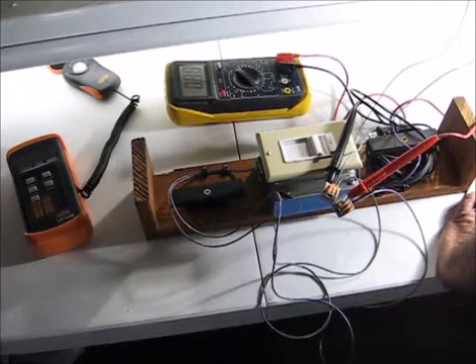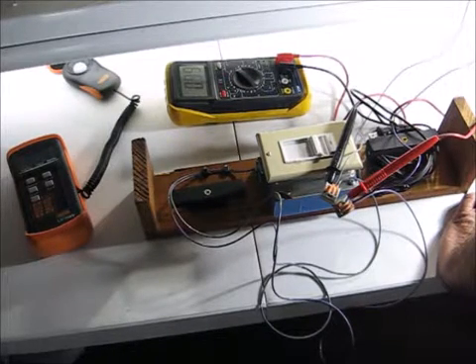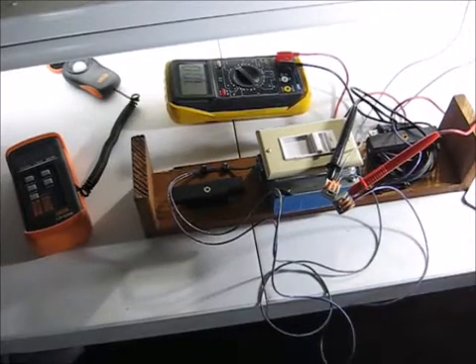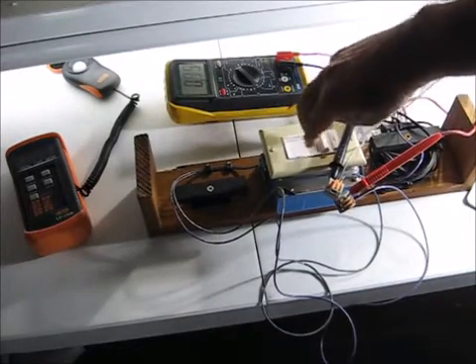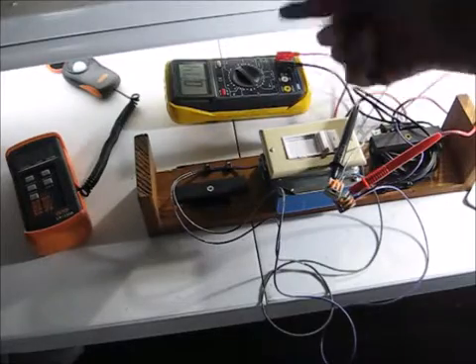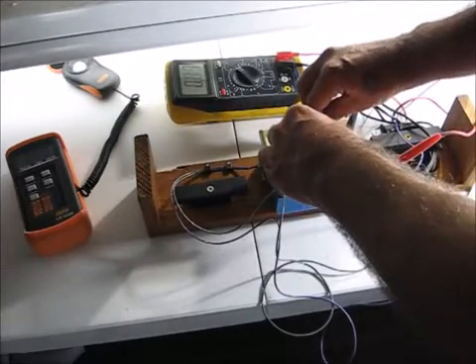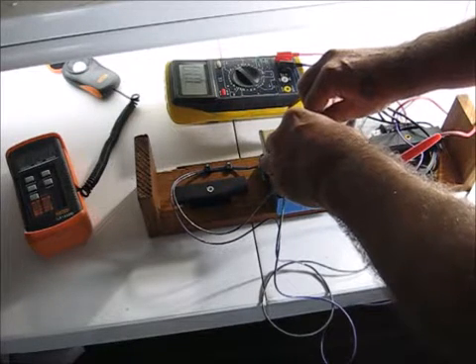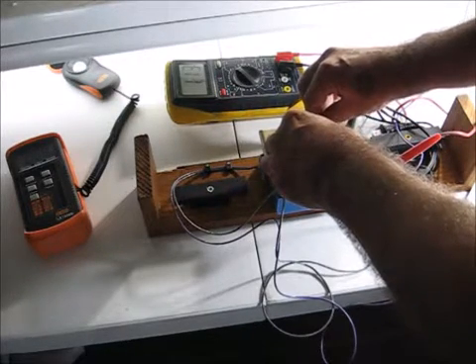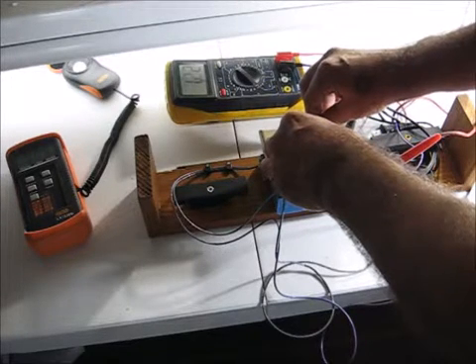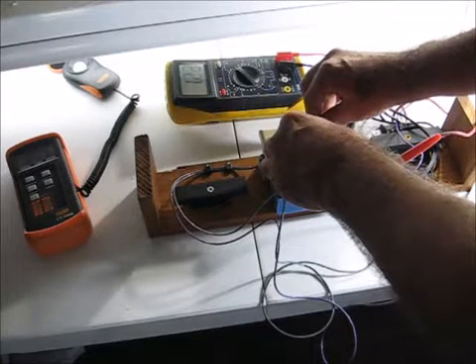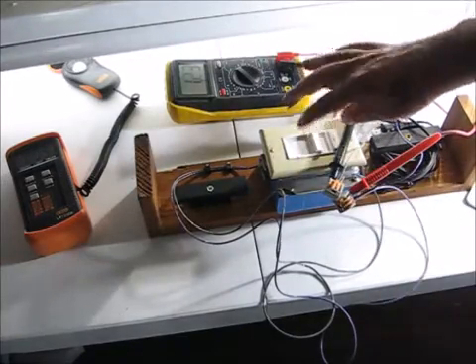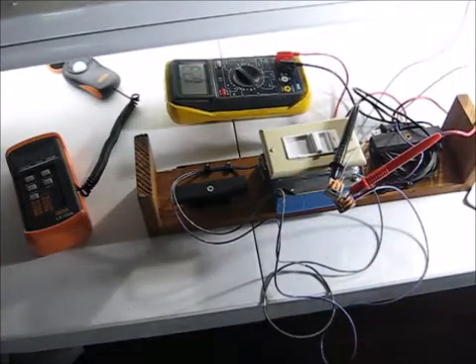So, your bottom end is basically a little bit above 1 volt, like 1.25. 9, 8. That's nothing anybody's going to see. I'll take it down to its minimum. No more dimming at 0.25 of a volt. So, I would go back and pick up, try and pick out that bottom end again. And let's see when it starts to dim up. Yeah, 1.25. 1.25 is basically where it has nailed on the bottom end.